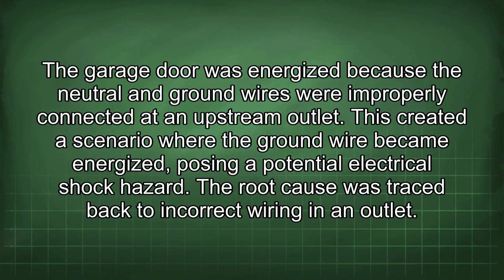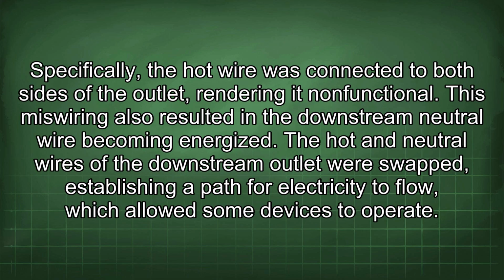The garage door was energized because the neutral and ground wires were improperly connected at an upstream outlet. This created a scenario where the ground wire became energized, posing a potential electrical shock hazard. The root cause was traced back to incorrect wiring in an outlet. Specifically, the hot wire was connected to both sides of the outlet, rendering it non-functional. This miswiring also resulted in the downstream neutral wire becoming energized.